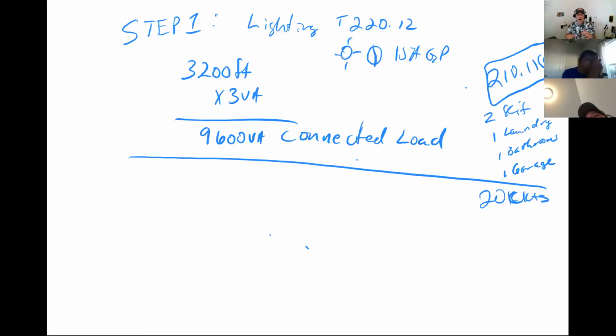220.52A says, all right, of those 5 20-amp circuits that I'm physically required to have, so in that panel in the garage, for example, I'm going to have 5 20-amp breakers. The rest could all be 15 amps for all I care, but I have to have at least 5 of those as 20 amps, one for each one of those sections.